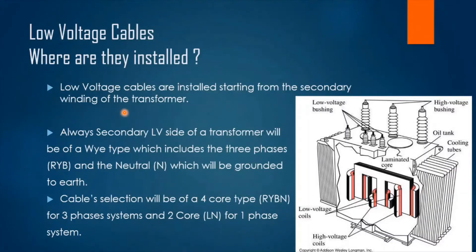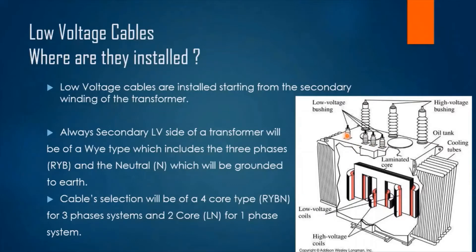Where are low voltage cables installed? Looking at this transformer picture, there is a primary side that carries the medium or high voltage cables, and a secondary terminal side which carries the low voltage side. These terminals are four terminals indicating three lines — L1, L2, L3 — and the neutral, which is also grounded to earth. According to this, we can use a four-core cable indicating three lines and a neutral for a three-phase system.